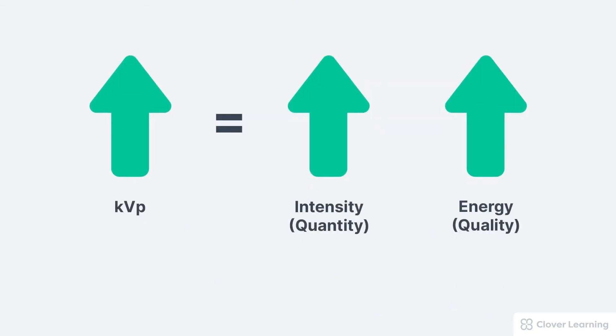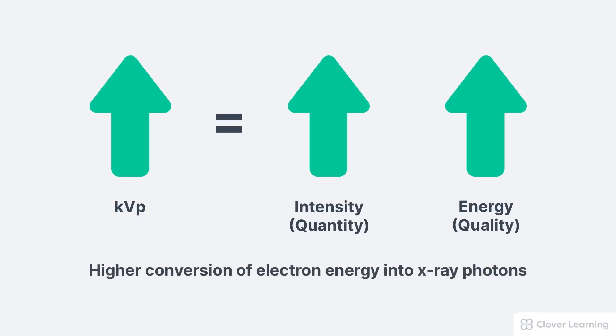KVP is the controlling factor for the energy of the x-ray beam, but it also has a significant influence on the quantity or intensity of the x-ray beam. This is primarily because higher KVP causes a higher percentage of electron energy to be converted into x-ray photons. Remember, only about 1% of electron energy in the tube is actually converted into x-rays. Increasing the KVP makes x-ray production more efficient, so more electron energy gets converted into x-rays.